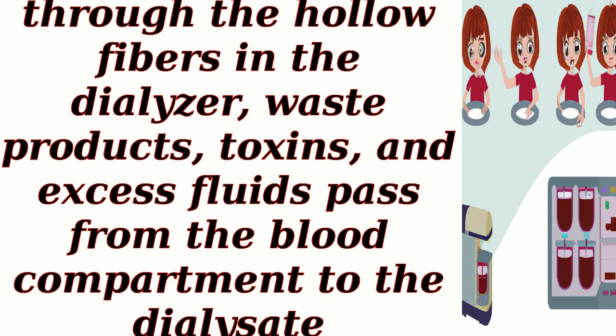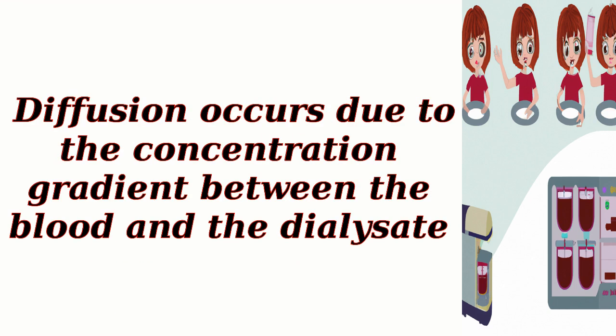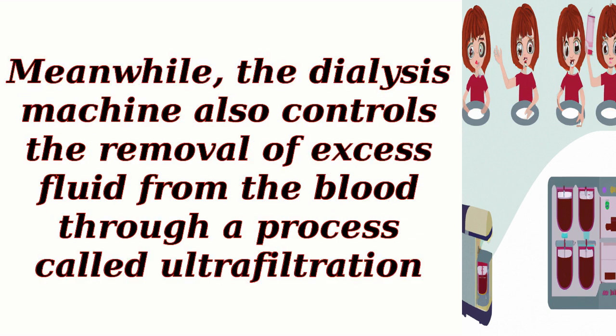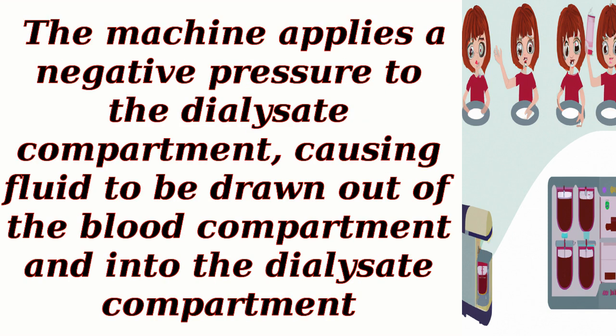Diffusion and ultrafiltration: as the blood flows through the hollow fibers in the dialyzer, waste products, toxins, and excess fluids pass from the blood compartment to the dialysate compartment through a process called diffusion. Diffusion occurs due to the concentration gradient between the blood and the dialysate. Meanwhile, the dialysis machine also controls the removal of excess fluid from the blood through ultrafiltration, applying a negative pressure to the dialysate compartment, causing fluid to be drawn out of the blood compartment and into the dialysate compartment.